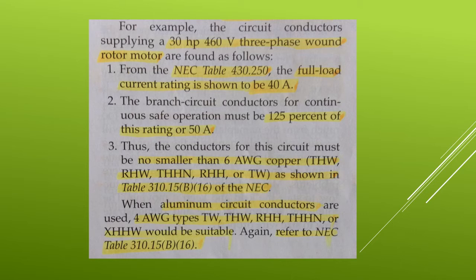Ampere adjustments and correction factors. You learned that the size of a conductor is based on the current rating of the OCPD, or the overcurrent protection device, and may increase if an adjustment factor or a correction factor is required. The adjustment factor is determined by the number of conductors in a raceway or cable, and the correction factor is based on the ambient temperature. Motor circuits must include an additional factor to handle the increased load as the motor starts. Article 430, Section 2 describes the situations where a conductor ampacity would have to be changed.